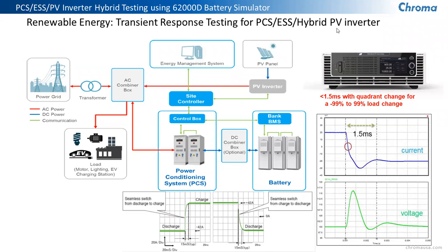And with that, we can use the 62000D products to simulate the battery used in your ESS. It's perfect because it can work to be a charging battery, a programmable charging battery, when the energy is either being fed from the grid or from the renewable energy source back through the controller and charging the actual batteries. It can also take the battery from our source in source mode and use it to output to the PV inverter, which then converts it to AC and puts it back out onto the grid. So perfect device for this.